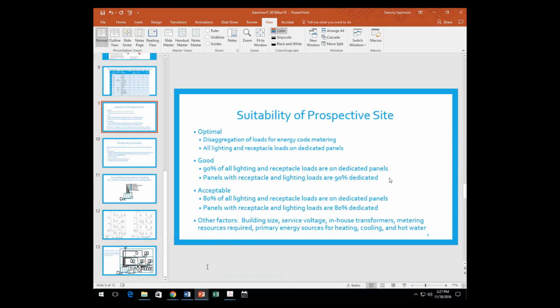Okay, I think the idea of what you're saying, Bob, is that you're addressing the 125% requirement for continuous loads on panels. Correct. Okay, and I've noticed that—say we have a lighting load and it might be, let's just say, 10 kVA, but the demand load is always like 12.5 kVA.